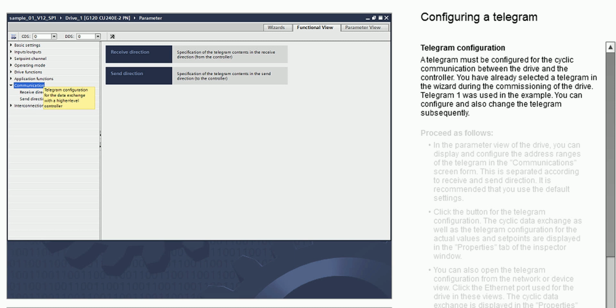Telegram configuration. A telegram must be configured for the cyclic communication between the drive and the controller. You have already selected a telegram in the wizard during the commissioning of the drive. Telegram 1 was used in the example. You can configure and also change the telegram subsequently.